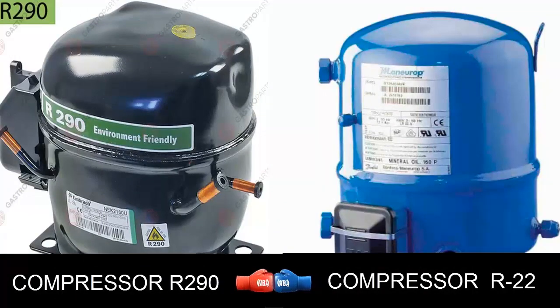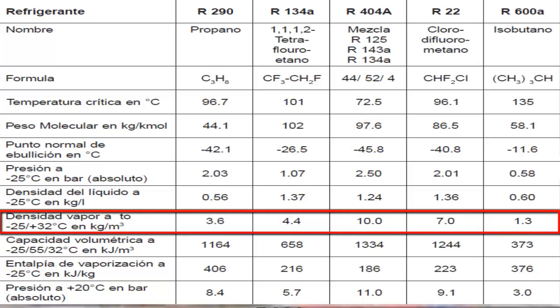The molecule of R22, in a vapor state, is heavier than that of R290. Therefore, with a slight increase in the volume of gas passing through the compressor, several grams of R22 will be transported. Although R22 is less efficient in cooling compared to R290, the greater quantity of grams passing through the compressor allows for sufficient cooling of the product.